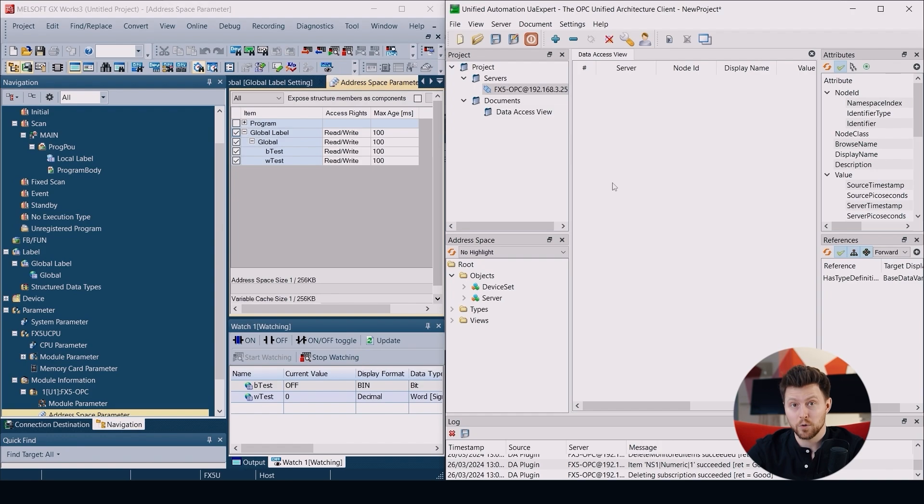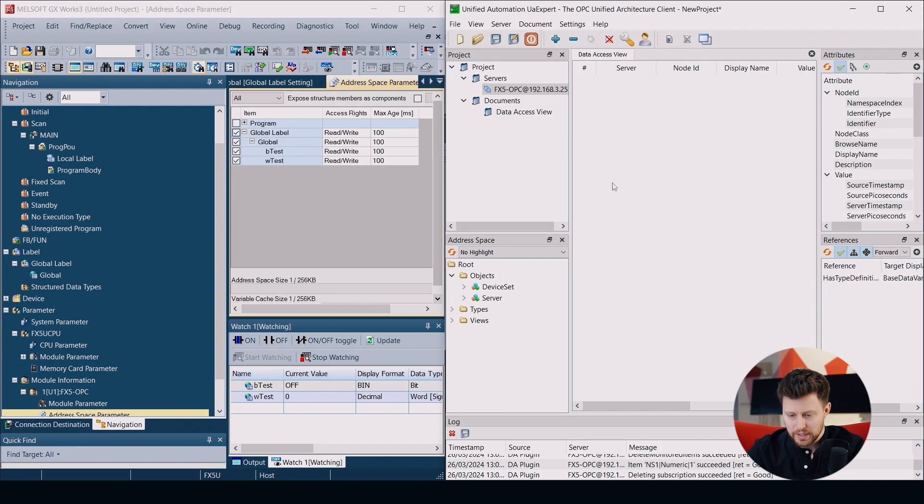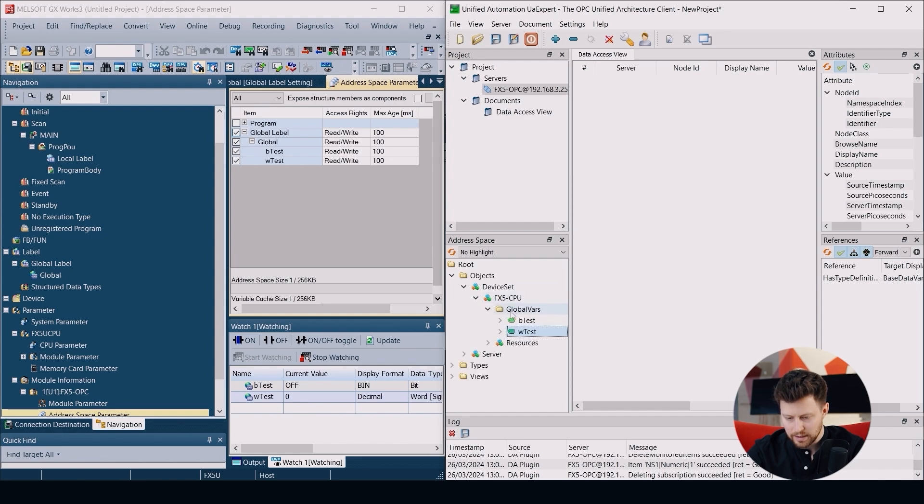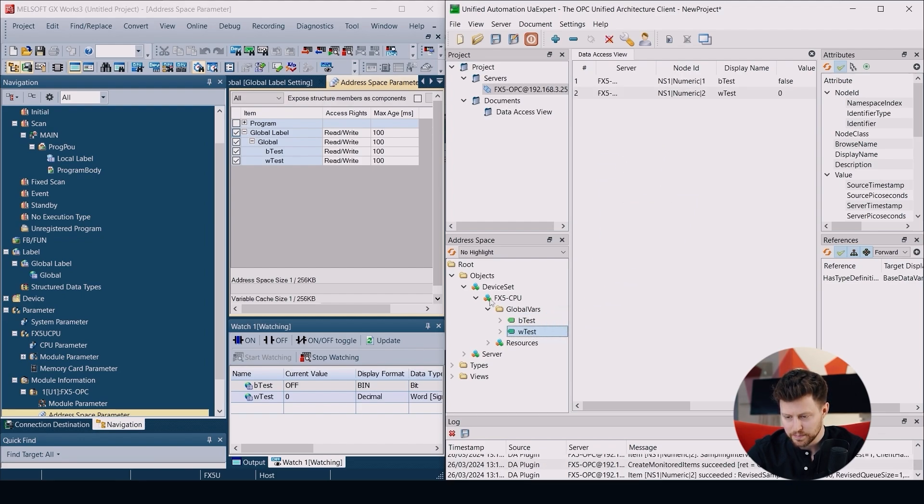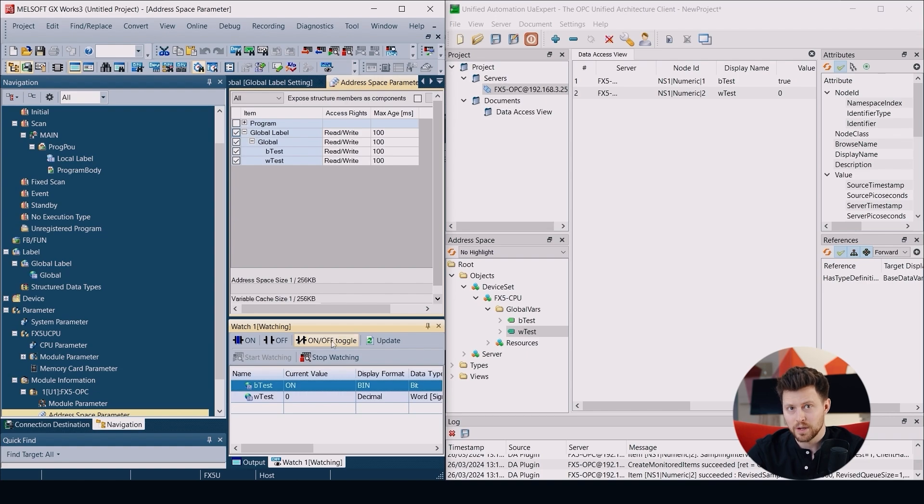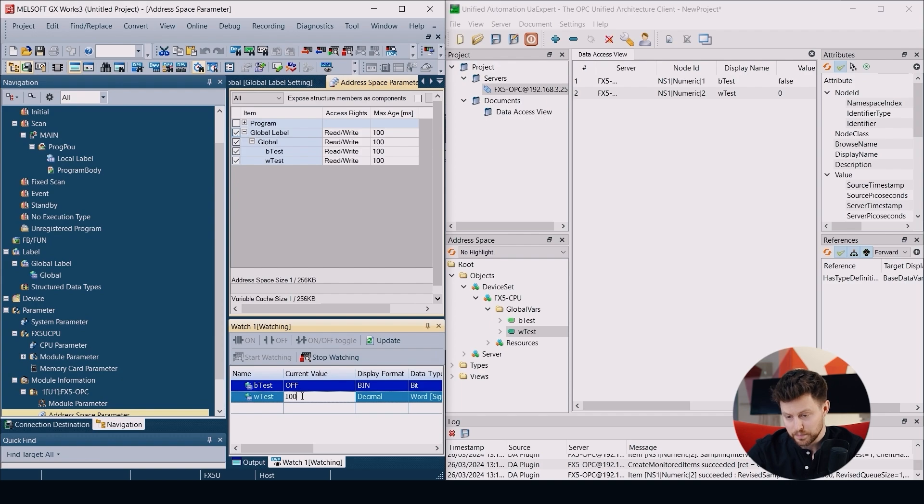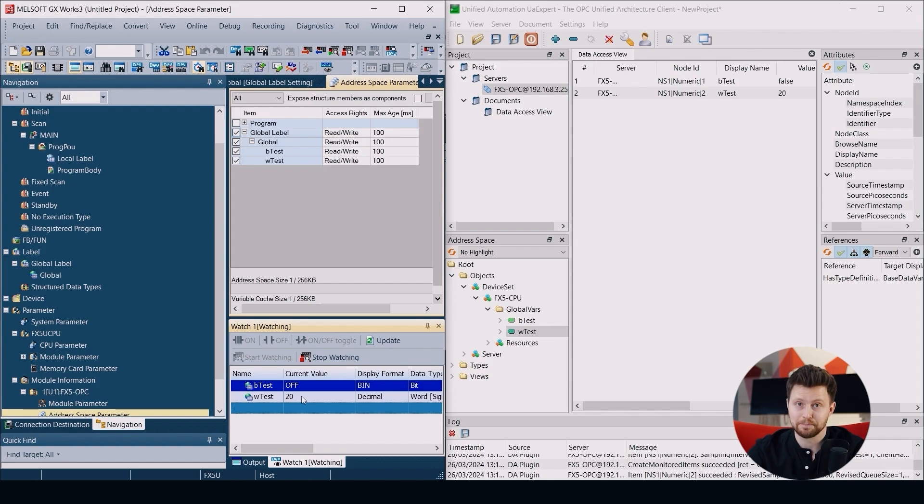So let's open GX Works 3 and UA expert side by side and we will check our communication. So when we click on our FX5 OPC server here we can go to objects, device set, and there is FX5 CPU. And here we can see our global values. When we put them to data access view we already see the values that we have in GX Works 3. When we change them we immediately see changes on our client side. So it works also for binary value, also for decimal. So yeah, everything is working correctly. So we did a great job.